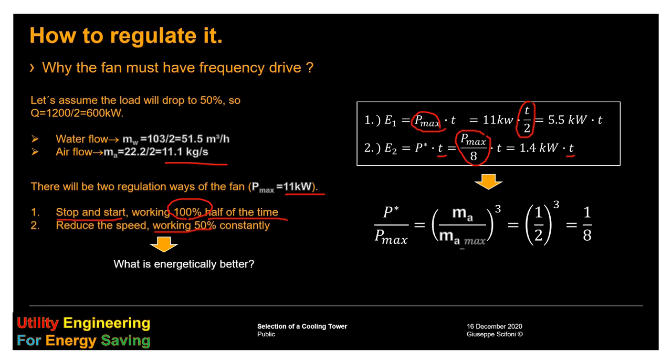Why? The reason is that between the power and the flow of a fan, axial fan in this case, there is a cubical law. So, the power is proportional to the cube of the air flow. In this case, the mass flow will be the half, so the power will be 1/8.